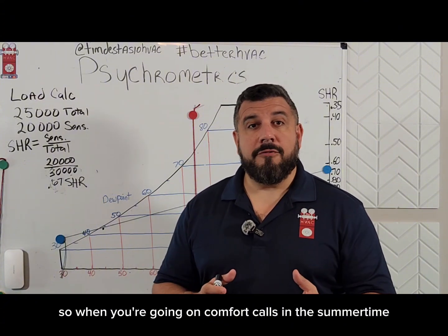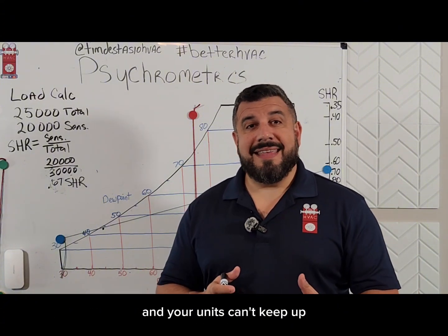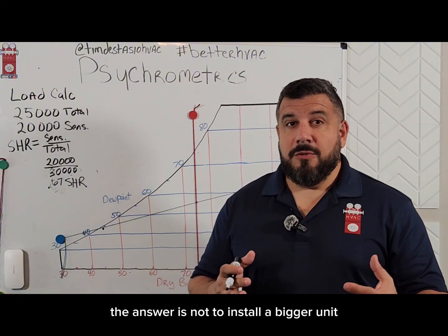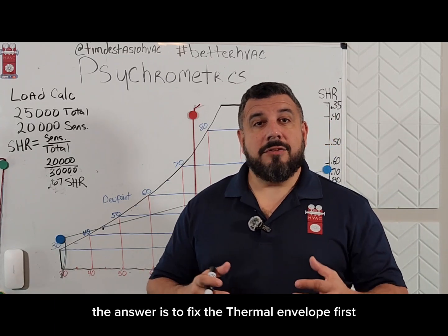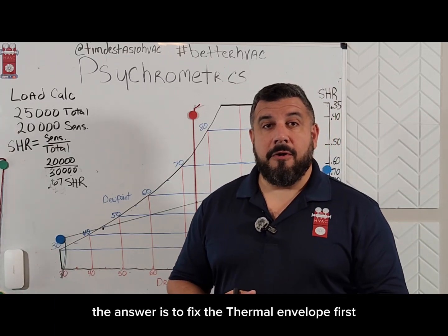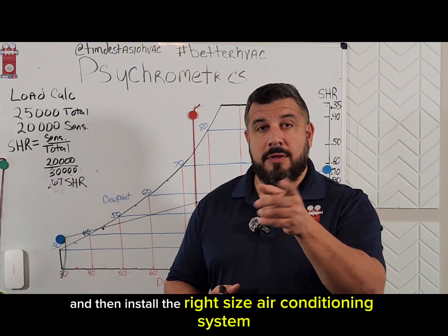So when you're going on comfort calls in the summertime and your units can't keep up, the answer is not to install a bigger unit. The answer is to fix the thermal envelope first, do a proper heat load calculation, and then install the right size air conditioning system.